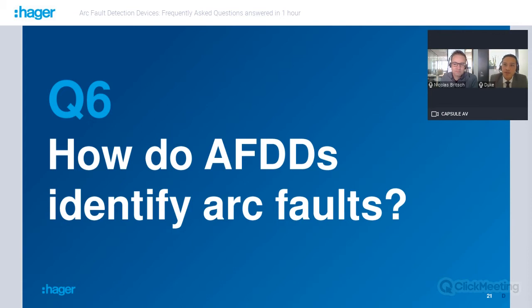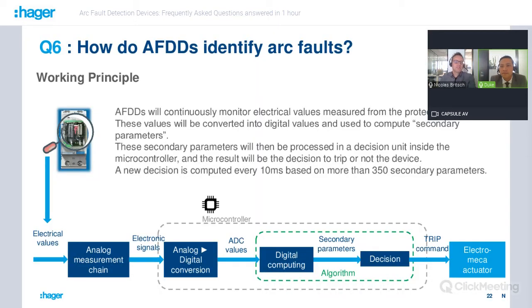Okay, so we see now the difference between short circuit and arc fault. Then question number 6 is, how do AFDDs identify arc faults in the circuit in order to order the tripping? Yes, so the working principle is explained here on this graphic. You have to know that AFDDs continuously monitor electrical values measured from the protected circuit. These values are converted into digital values and used to compute what we call secondary parameters. For example, the RMS value of the current is a secondary parameter because it's computed from the raw signal of the current. These secondary parameters are processed in a decision unit inside the microcontroller, and the result is a decision to trip or not the device. And a new decision is computed every 10 milliseconds, which is a half cycle for 50 hertz electrical mains.